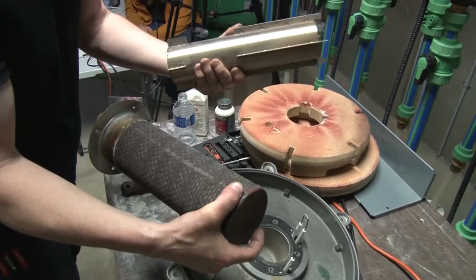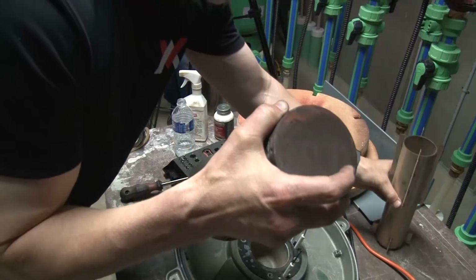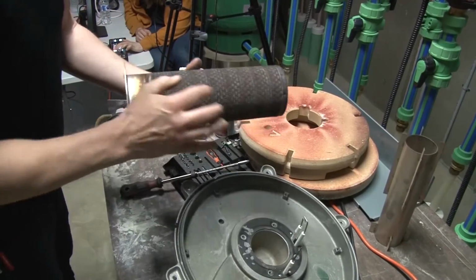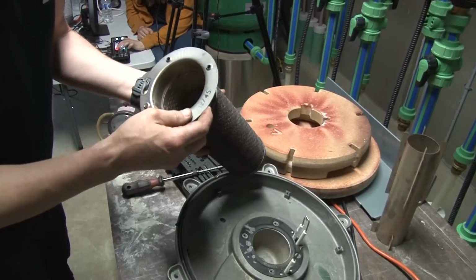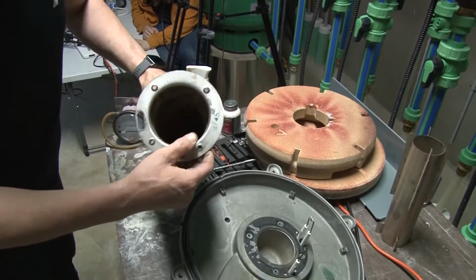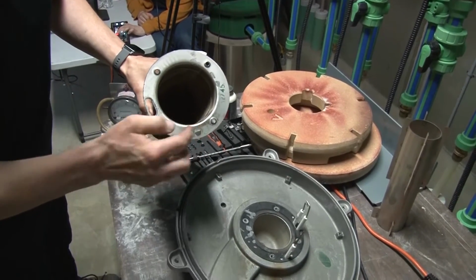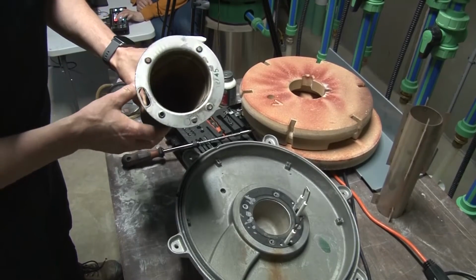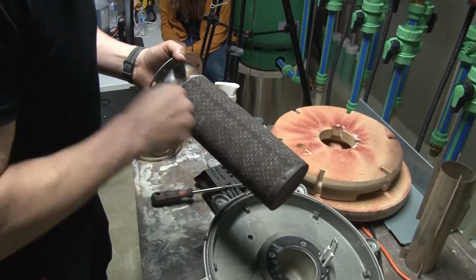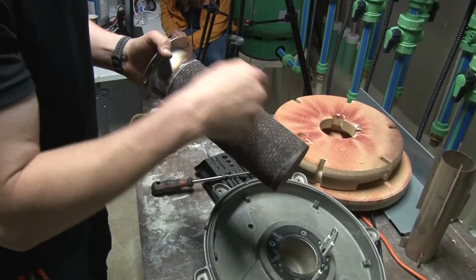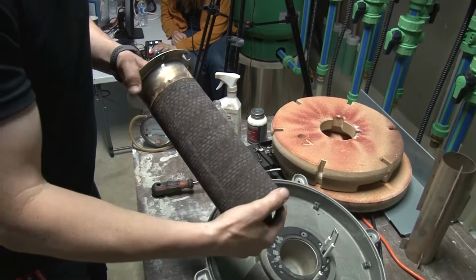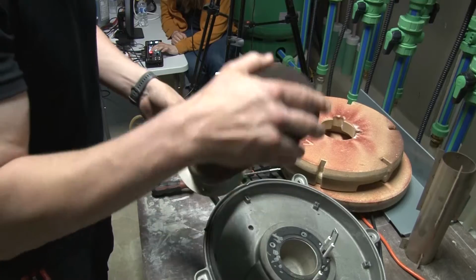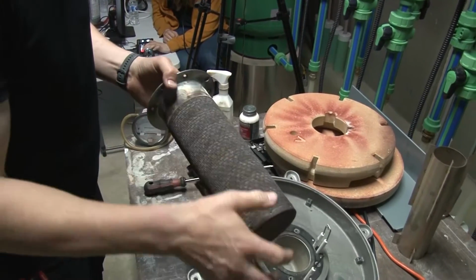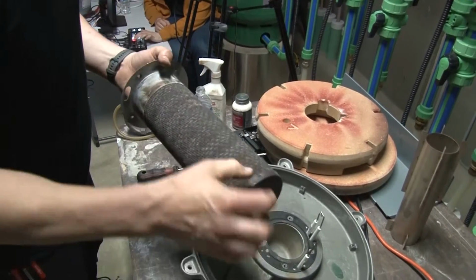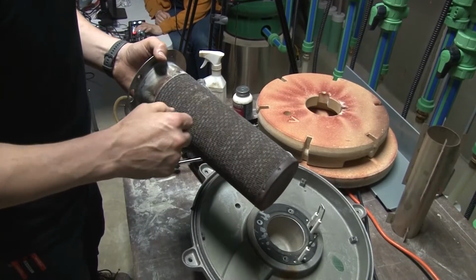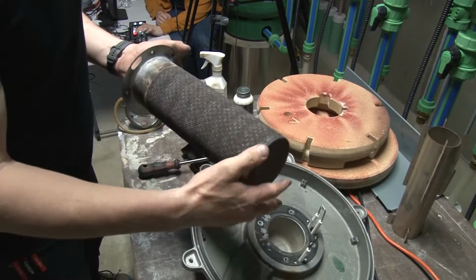You can see a little bit of dust and debris on that. That's not going to be of any issue as far as operation, but we really want to hone in on the mesh here. It looks like it's in pretty good shape. You can kind of see where the ionization electrode sits, also where the spark electrode sits in there. You can vacuum it off, and we're not really scrubbing with a vacuum cleaner. It's just a light, basically, kind of brush of that, and just getting any debris off of that. I'll do a little bit now, but after I put the refractory back on, sometimes you catch a bit of the refractory on this mesh. So I'll have to vacuum it again.